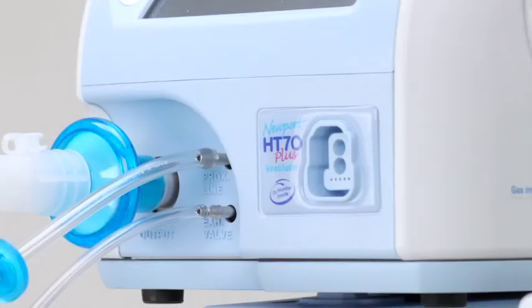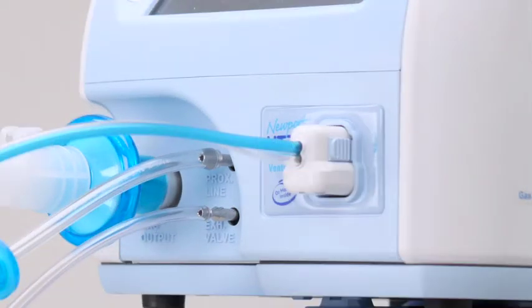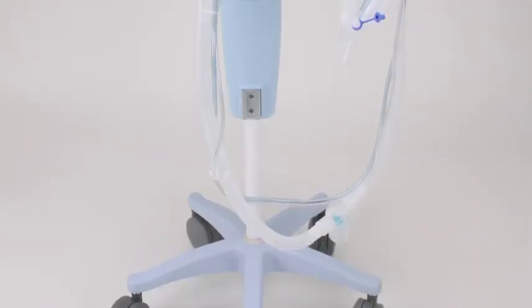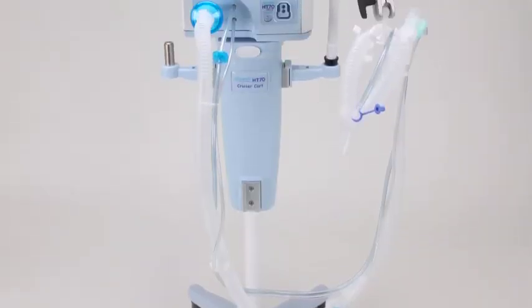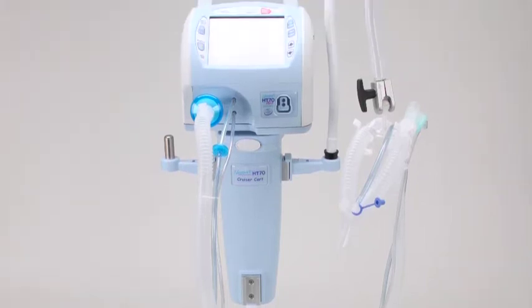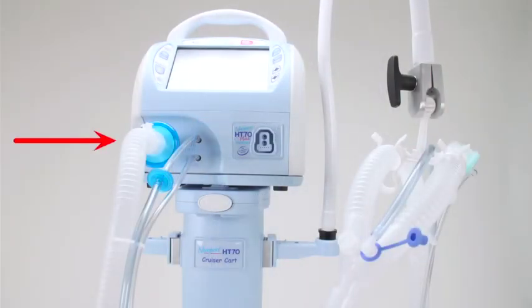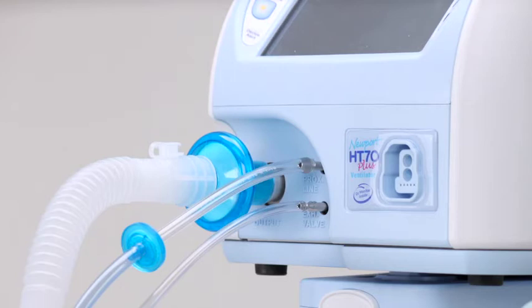The first choice you need to make is whether or not you will use the on-airway flow sensor. The setup is very easy either way. Here is an example of how the circuit setup looks without the on-airway flow sensor in place. The main part of the circuit tubing is connected to the main flow outlet, and the smaller exhalation valve and proximal pressure lines are connected to the smaller fittings, just to the right of the main flow outlet. Notice that I have two filters installed. One is on the main flow outlet, and the other is on the proximal line fitting.